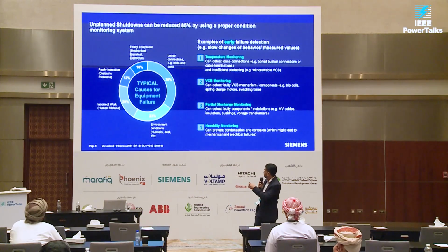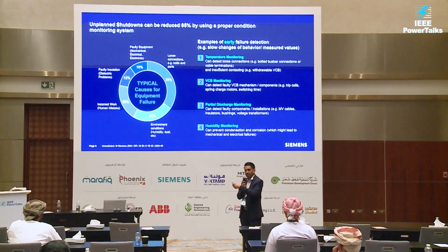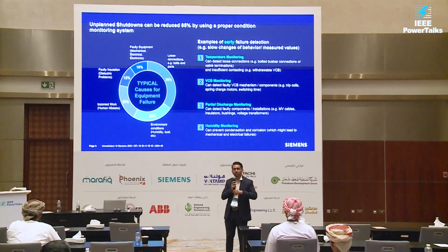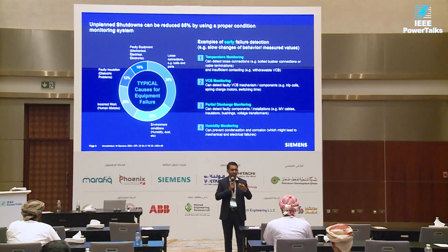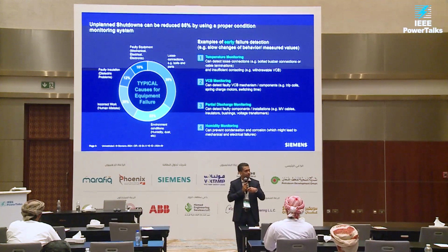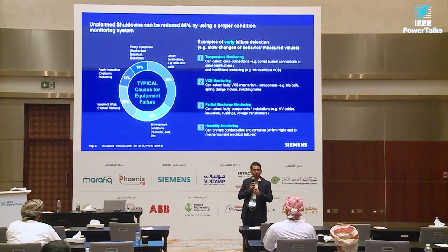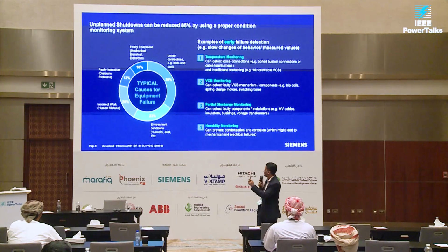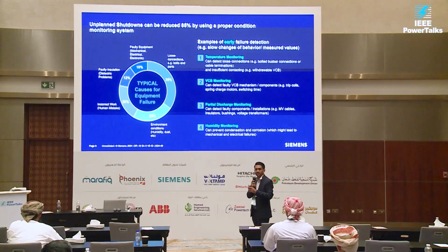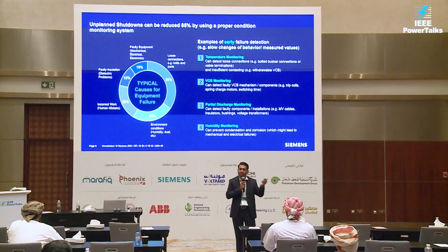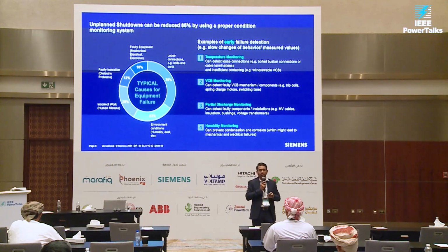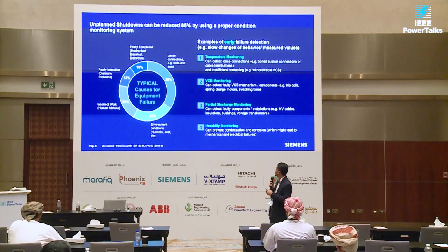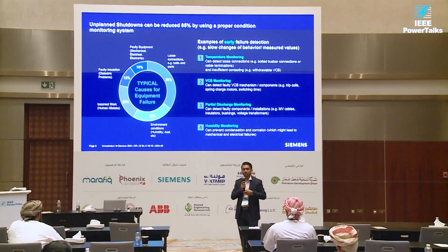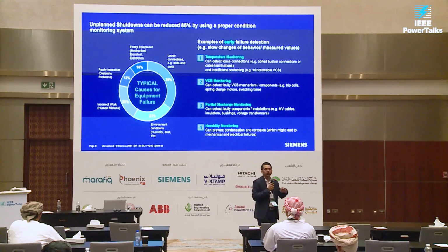So to monitor all these things automatically, instead of relying only on periodic maintenance and expertise of respective engineers, we can do it automatically, that we install certain sensors on the switchgears. We do different modules, like for example, as basic as temperature monitoring, which could have avoided what we saw in the previous slide. This could have been avoided by doing temperature monitoring. We can monitor circuit breakers, we can monitor partial discharge, we can monitor humidity.